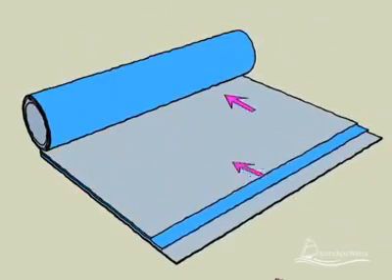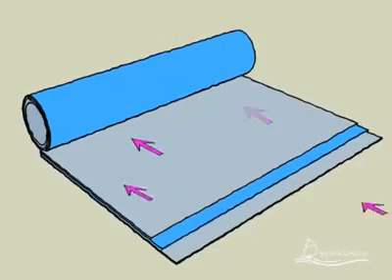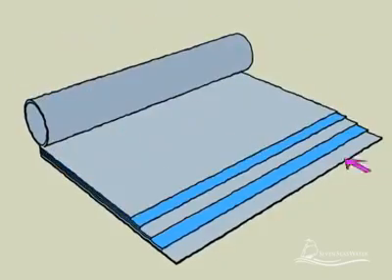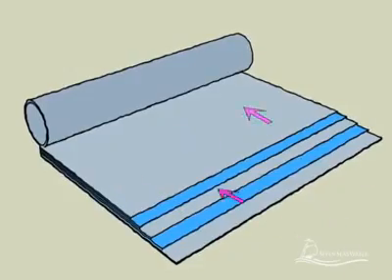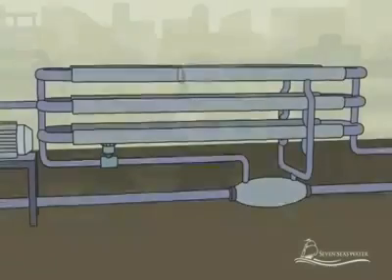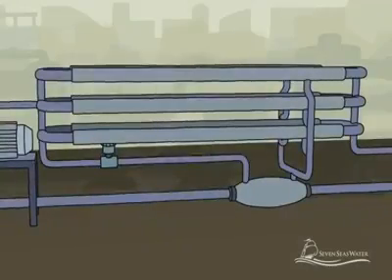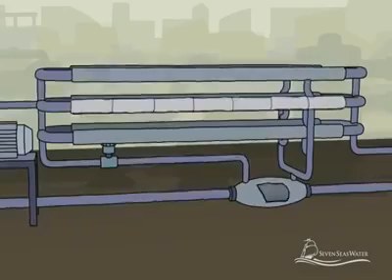The reverse osmosis membrane can be thought of as a number of sealed envelopes connected at their open ends to a tube. There are spacers between each envelope which allow water to flow across the membranes. The membrane envelopes and spacers are then wound around the tube like a roll of paper towels. The reverse osmosis membranes are then enclosed in a fiberglass shell, connected end-to-end — usually six to seven membranes together — and housed in vessels built to withstand pressures up to 1,200 psi.